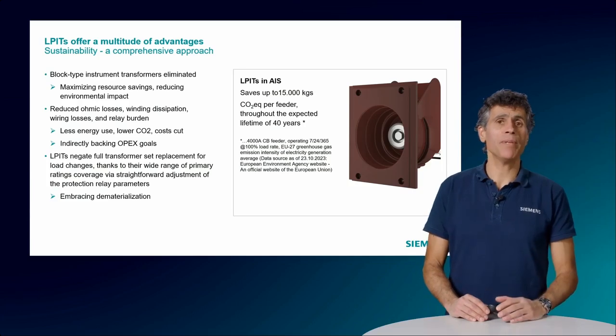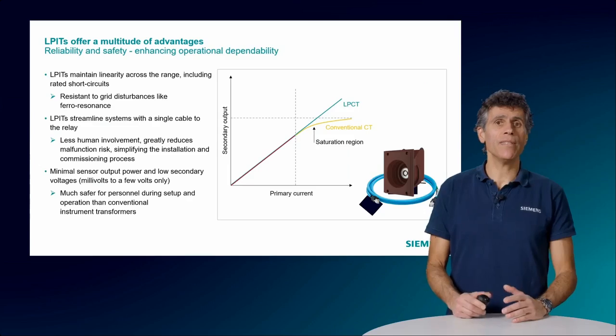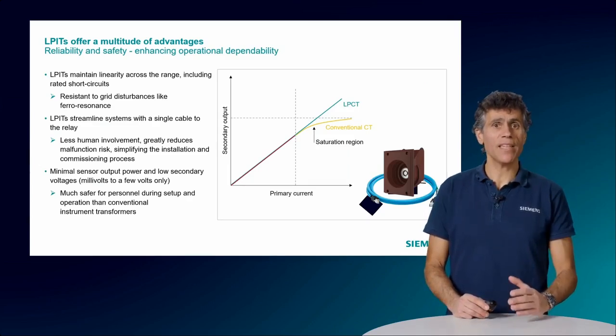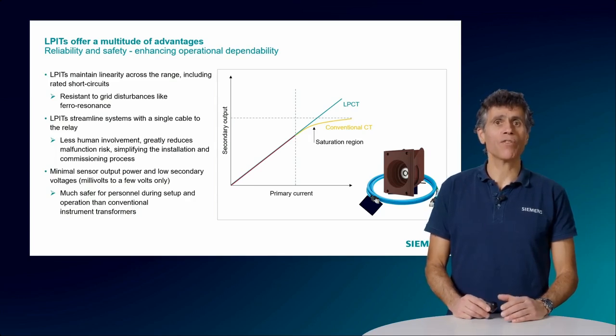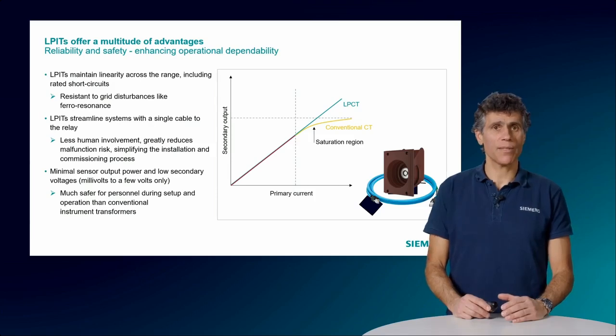Fifth, LPITs are reliable. The sensors are immune to grid disturbances such as ferroresonance phenomena. They are linear over the whole measuring range, even up to the rated short-circuit fault currents. This goes along with a higher accuracy in measurement when compared to the classic block transformers.